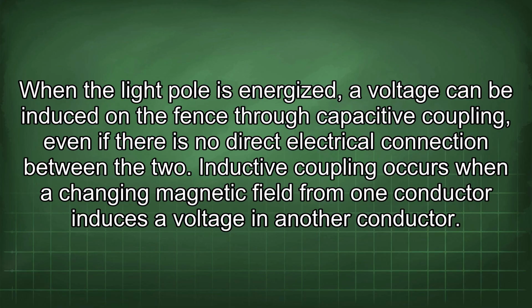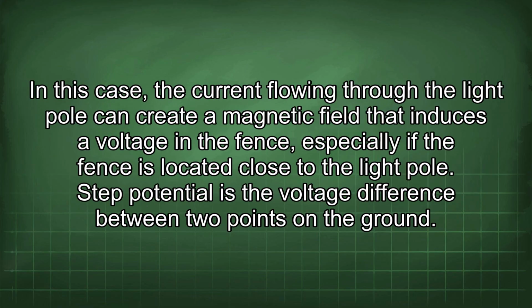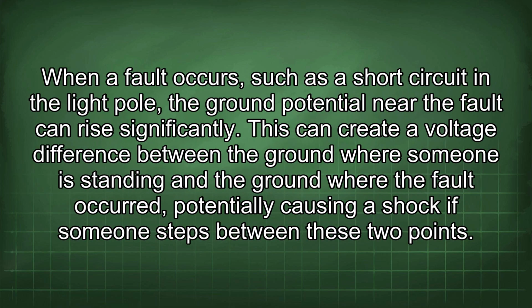Inductive coupling occurs when a changing magnetic field from one conductor induces a voltage in another conductor. In this case, the current flowing through the light pole can create a magnetic field that induces a voltage in the fence, especially if the fence is located close to the light pole. Step potential is the voltage difference between 2 points on the ground. When a fault occurs, such as a short circuit in the light pole, the ground potential near the fault can rise significantly. This can create a voltage difference between the ground where someone is standing and the ground where the fault occurred, potentially causing a shock if someone steps between these 2 points.